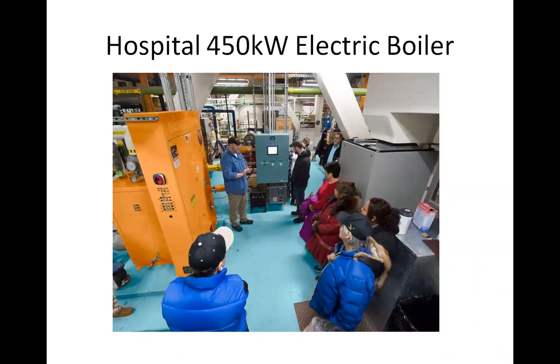So what we're doing is operating the elements based on how much load we can provide. It's worked quite well — there's 450 kW of power there, and we've achieved that pretty regularly. It's also achieved long run times where they're not operating their oil-fired boiler at all. I think there's been some 24 to 36 hour periods where they've just been running on excess wind power to heat the hospital.